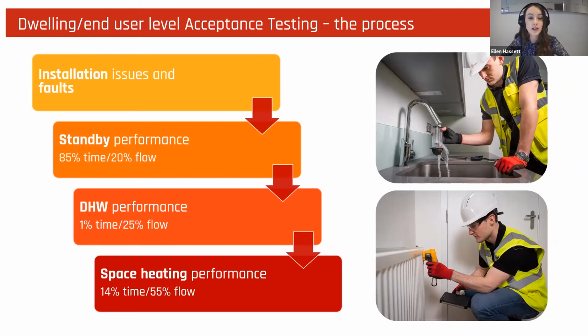First, we look at installation issues and faults, such as insulation quality. So the final run to HIU accounts for up to 50% of the overall network. And despite this, it's the most common for it to be insulated poorly. So we'll look out for the insulation standard, amongst other faults such as heat meter errors.